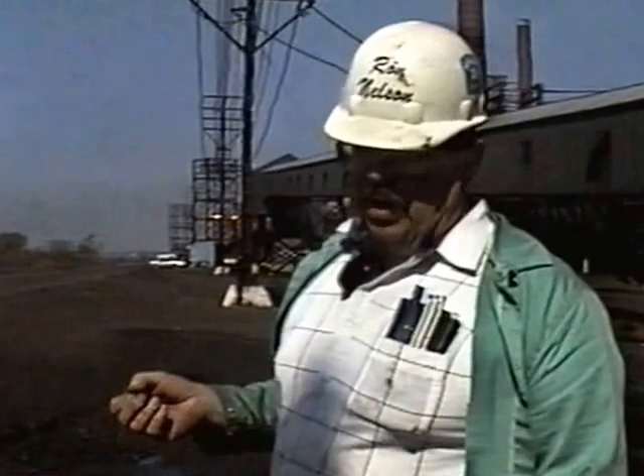The diesel fire pump, if we use it, must also be drained, especially in the wintertime. We have had problems with the diesel pump over the years, freezing and the piping breaking because we have not drained it thoroughly. It should be done every time we use it, and prepared as though it was wintertime.